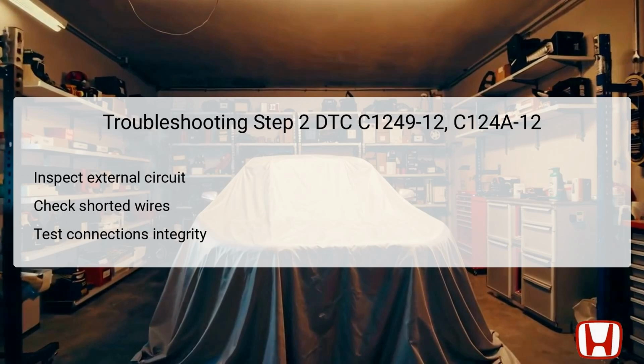This step is critical as it ensures that the external circuit is functional. Also, use a multimeter for continuity testing to confirm each connection's integrity. Ensuring there are no shorts in the wiring is vital for diagnosing the root cause of the detected issues.